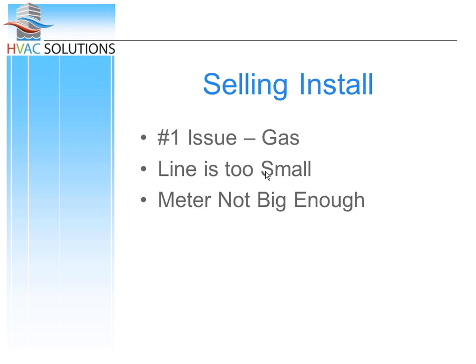One thing I like to always bring up when talking about generators is selling the quality of the install. The number one issue that Generac gets is that the gas line is too small. I can tell you horror stories of gas lines tapped off after the furnace and a half-inch gas line run to a 20 kW unit - they don't understand why it won't start. So the gas line is too small.